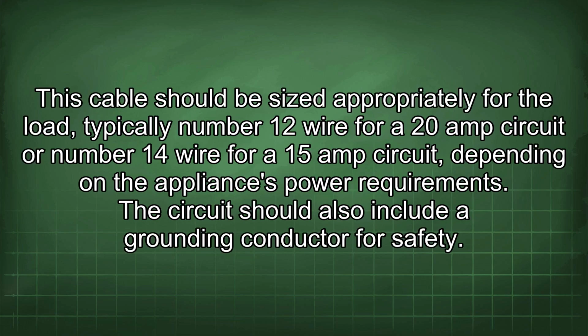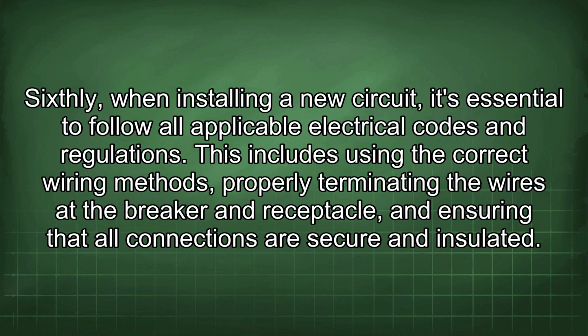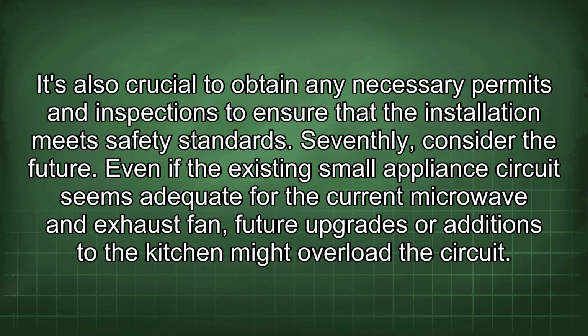This cable should be sized appropriately for the load, typically number 12 wire for a 20 amp circuit or number 14 wire for a 15 amp circuit, depending on the appliance's power requirements. The circuit should also include a grounding conductor for safety. Sixthly, when installing a new circuit, it's essential to follow all applicable electrical codes and regulations. This includes using the correct wiring methods, properly terminating the wires at the breaker and receptacle, and ensuring that all connections are secure and insulated. It's also crucial to obtain any necessary permits and inspections to ensure that the installation meets safety standards.